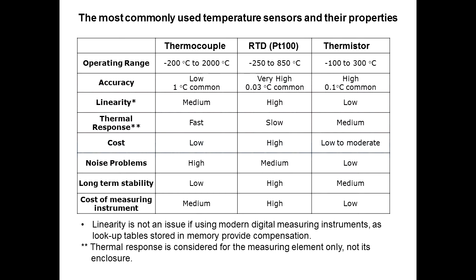So the advantages and disadvantages: thermocouples operate over a wider range. RTDs will go lower than a thermocouple on the bottom end, but they won't go as high on the top end. Thermistors are generally low or short range span, but the accuracy can be very good. RTDs are best on linearity, you can see the differences. Thermal response, RTDs are slow compared to the other two. Cost, RTDs are higher compared to the other two.